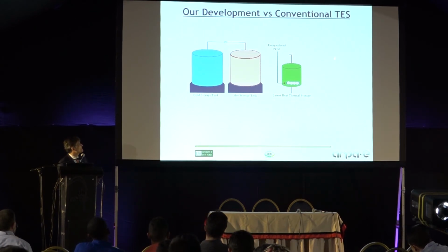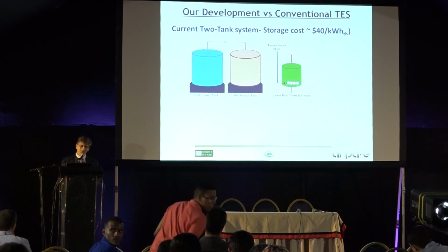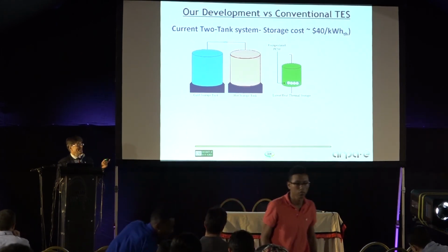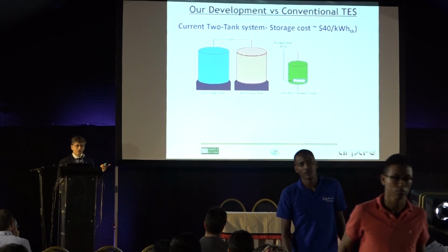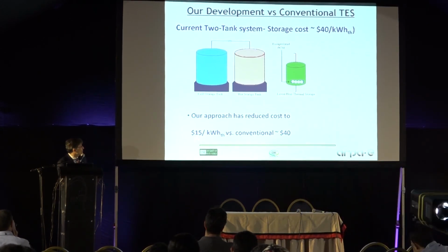And this is our thermal energy storage. Not only do we not have two tanks, now we have only one tank. And that one tank is 1/4 of one of these tanks. So with that improvement, the current cost is $40 a kilowatt hour thermal. We reduced it down to $15 a kilowatt hour thermal.